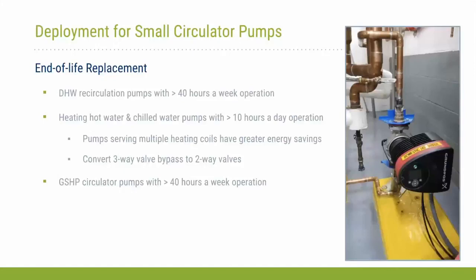The heating and chilled water pumps, you want to look at systems that operate more than 10 hours a day. Those can be challenging because if your cooling system only runs for 4 months per year, it has a lot less operation than a domestic hot water pump that's running all year long. So you need to look at how many hours per year it's running.